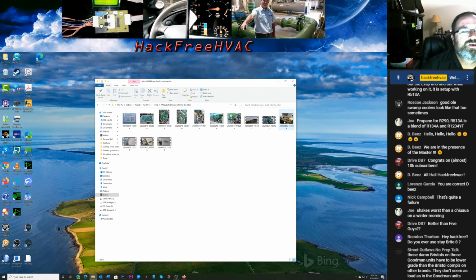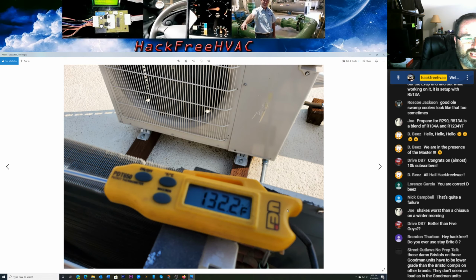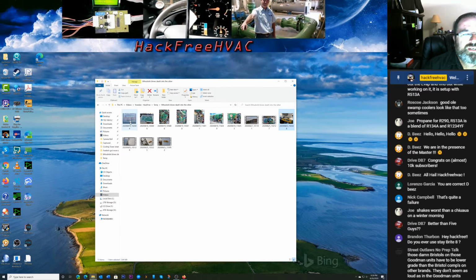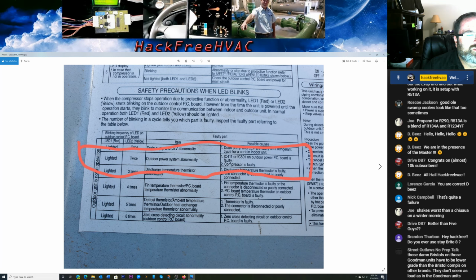So here's a little adventure. I showed you guys one of the photos here yesterday or whatever it was. 132 degrees where I was working in the shade. You see that's shaded by my umbrella. That's because this unit here, it's not as close as it looks, it was like 3 foot, 40 inches or so, but it was just blowing its hot air right on it. So it's no wonder that I had this fault on this Mitsubishi.